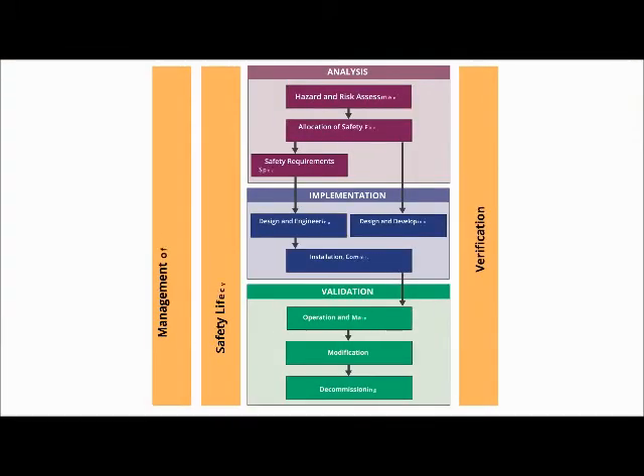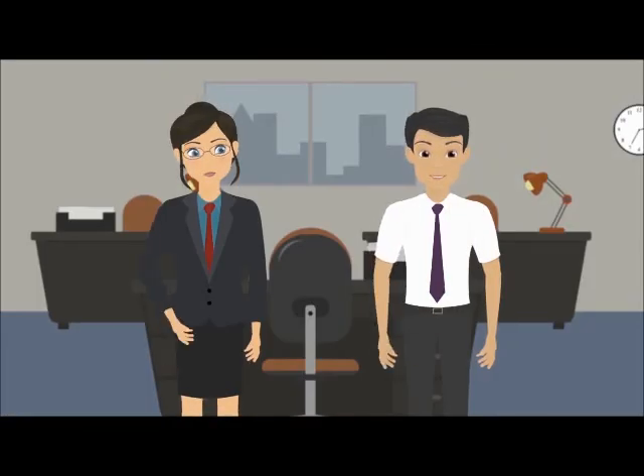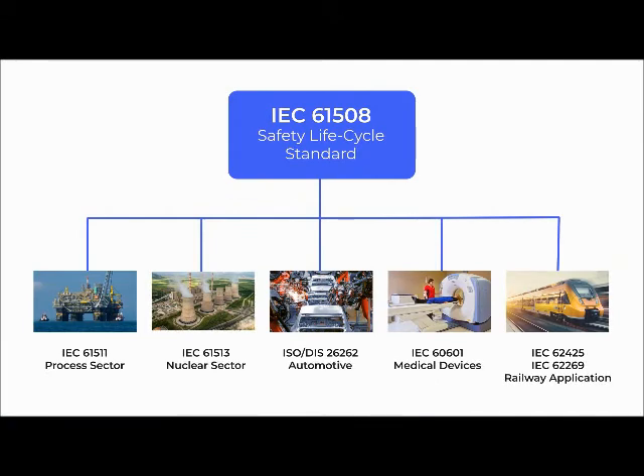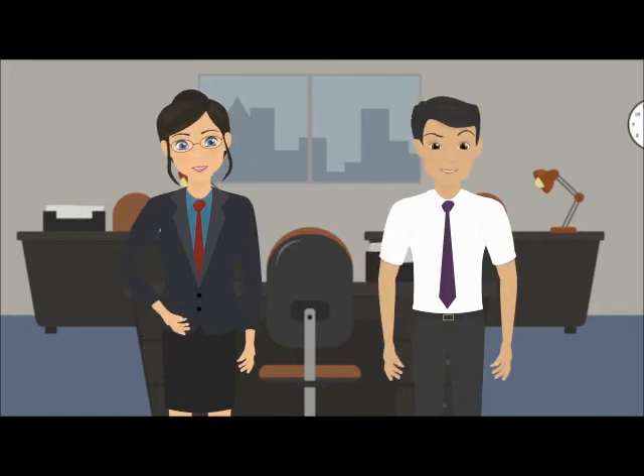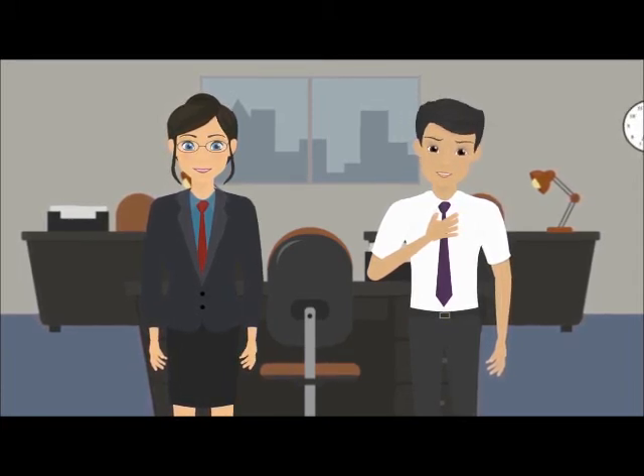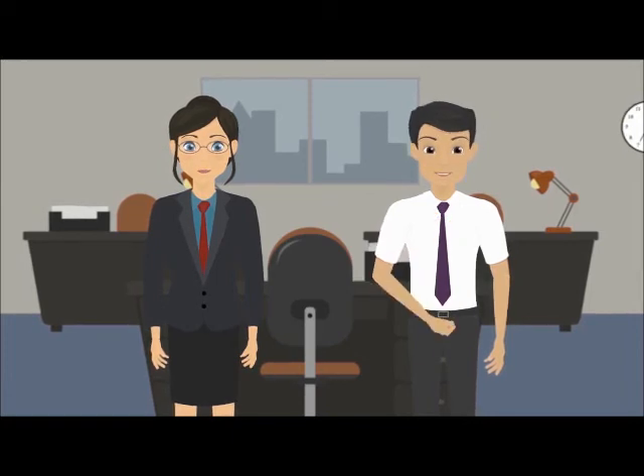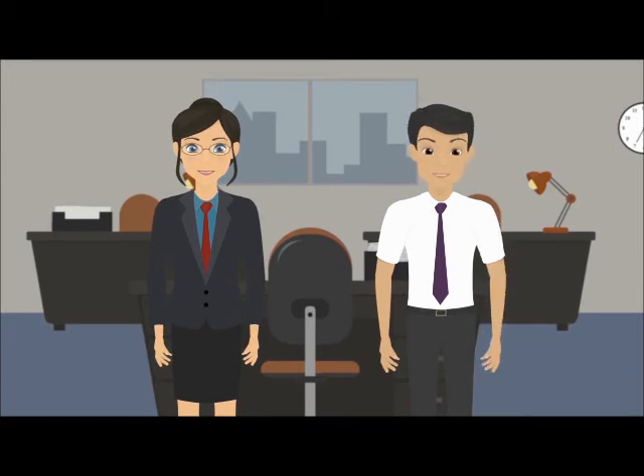There are standards which answer all your questions. What are those standards? There is an umbrella safety standard called IEC 61508 and sector-specific standards, like one for process, one for machinery, one for nuclear, etc. Which is the standard for process industries? It's called IEC 61511. So, if I'm in the process industry, I need to follow IEC 61508 and IEC 61511? Yes. They prescribe ways to meet the functional safety requirements? No — both standards are performance-based and not prescriptive.